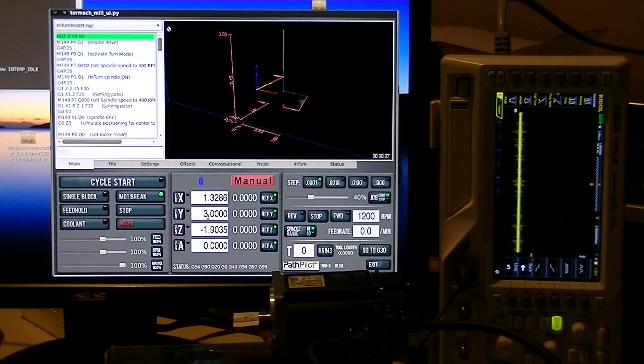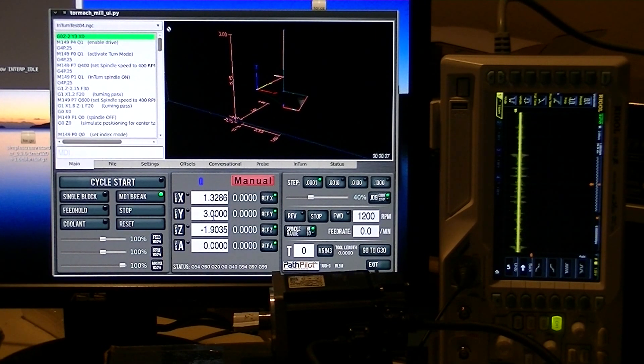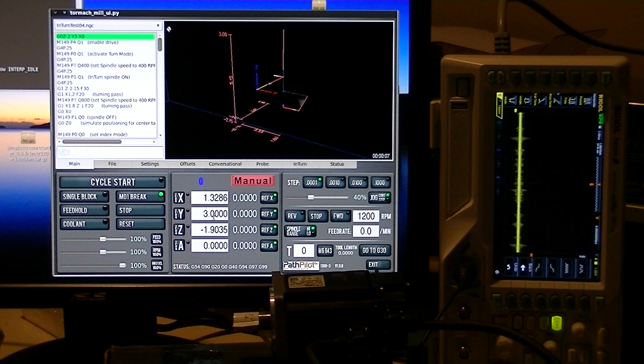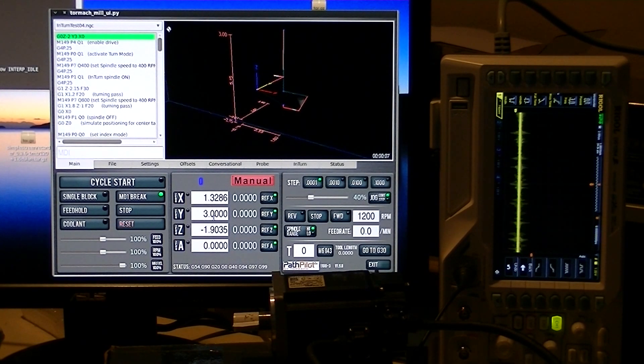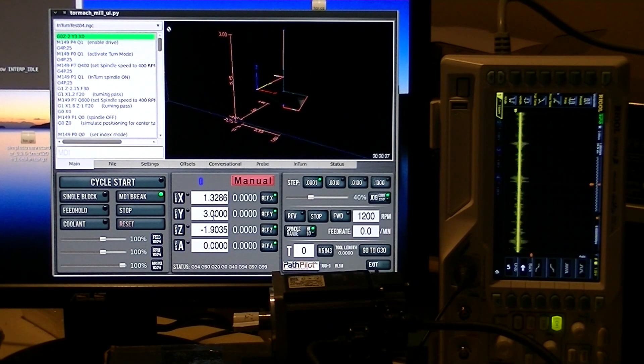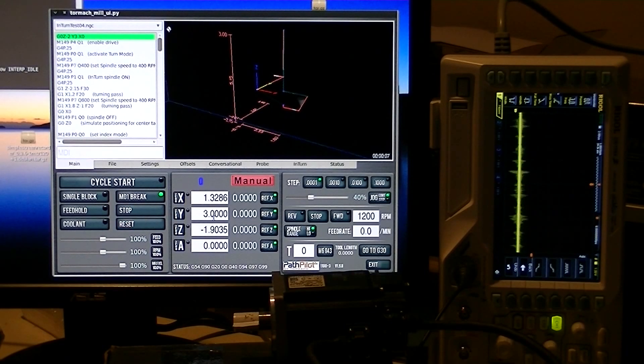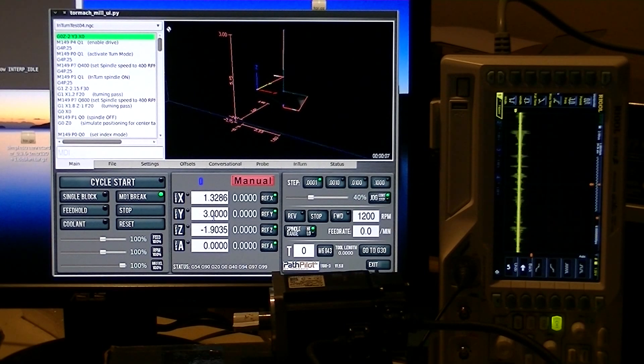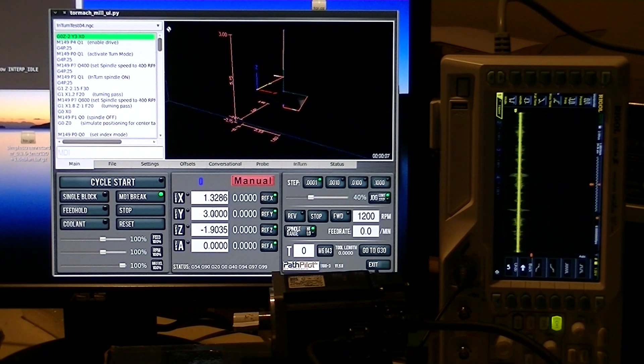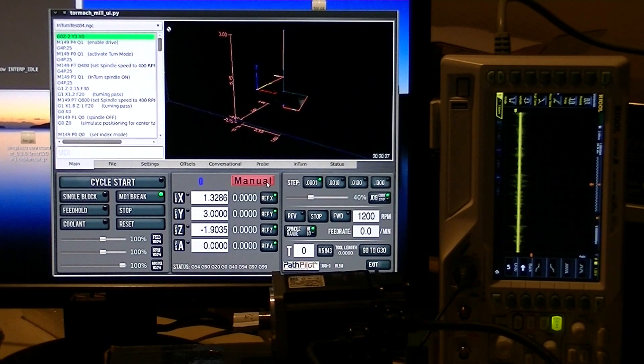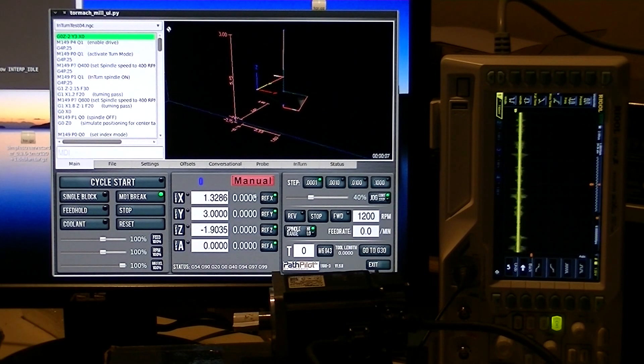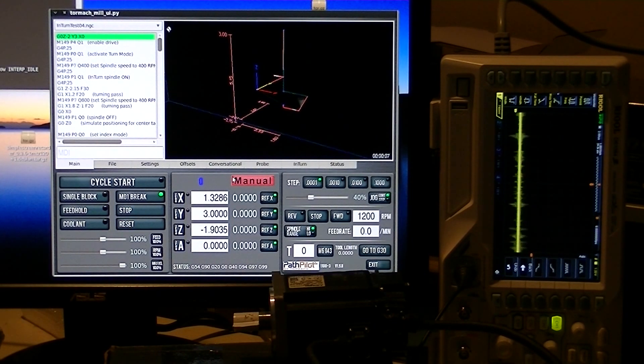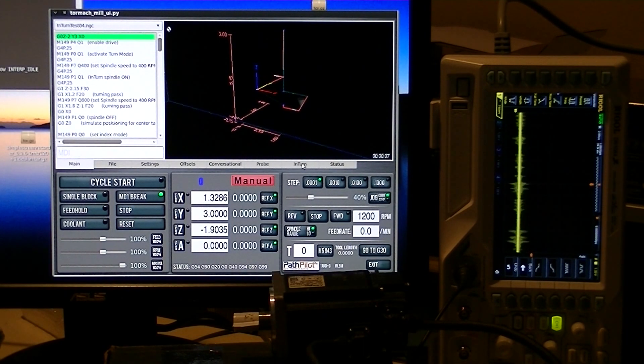Interp has sent a signal over to the controller to inform the controller that it's in an E-stop condition. When you're in a mode where the motor is spinning, the controller has control of the motor, so it has to be informed of the E-stop because only it can stop the motor spinning at that point.